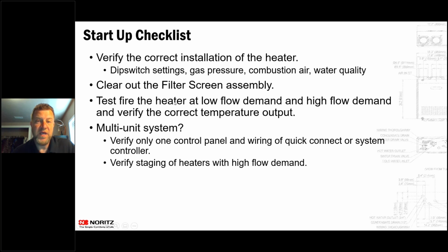Once you first start up that unit, especially if you're doing a retrofit and they have galvanized lines, run the unit for a few minutes, then turn off the water and check the filter going into the unit. If it's old copper lines too, they might have a lot of scale in them that, with you working on it, is knocking things off. Just make sure that the incoming filter screen is cleaned out before you leave. If that thing gets too gunked up, you're not going to get flow through the unit, it's not going to fire, and you're going to get a callback on that. Make sure that you test fire the unit at low flow demand and at high flow demand. Low flow is just turning on one single faucet and making sure everything's going. High flow demand is turning on two or three tubs and making sure everything is going.